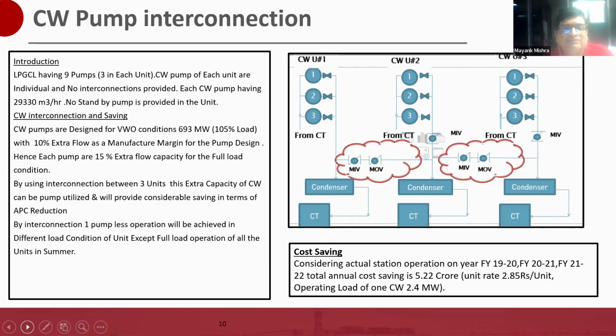However, we observed that with 9-pump operation, the condenser vacuum actually comes down, whereas with 8-pump operation we are able to maintain a sufficient, economical condenser vacuum. Our design value is 0.1 kg/cm² absolute pressure, but as per our calculations and other economical factors, we are able to generate 0.08 kg/cm² absolute pressure with 8-pump operation, without needing 9-pump operation.